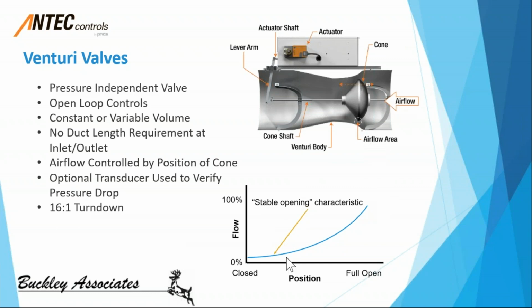Now, the nice thing about this is we don't have that low end inaccuracy. So as this valve fully closes and gets further down into this body and reduces the airflow, we're still going to have stable opening. Okay, so we don't lose that accuracy as we approach the minimum airflow allowed through this valve.